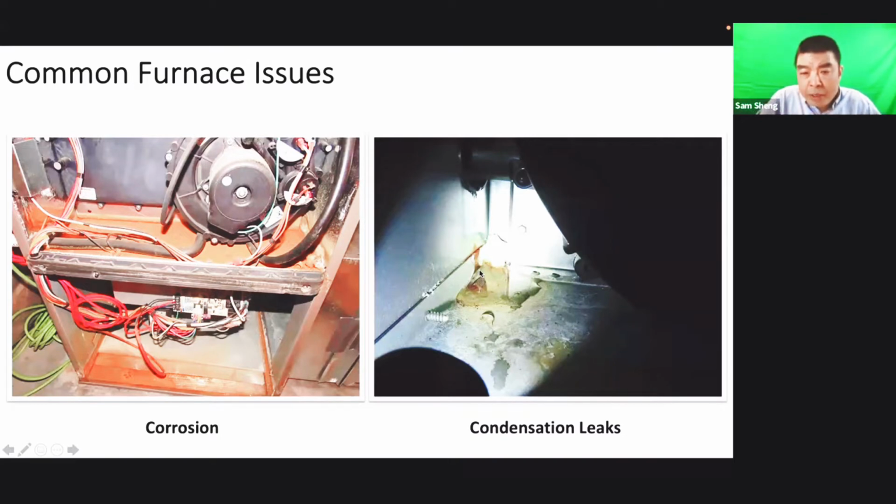But normally you can trace the water drain, like this mark here. I don't know if the water comes from here. If it comes from here, that should look like condensate water from the furnace. If not, maybe it's the humidifier or A coil. Okay, this set is for the furnace category 4. If it's category 4, maybe it's just the condensate water drain system clogged, causing the trouble.